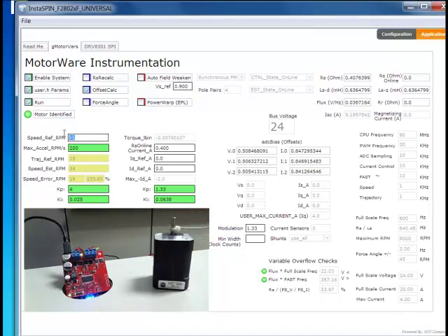And I'll go ahead and try half a hertz. You can see it's basically gone at that point. It's still stable in the sense that it hasn't totally crashed, but it's not giving you performance. So we kind of are at the 1 hertz mark for this motor with this inverter combination.